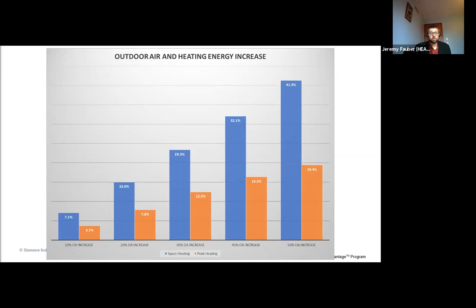I want to draw a little bit of attention to the orange. While this looks like it has a lower impact on the heating equipment, if you look at the percentages, all of them are actually higher than the cooling. So even at the 10%, there's this 3.7% increase in peak capacity versus 19.4% at the 50% air increase. So this again has your impact to that equipment that you've got to look at.